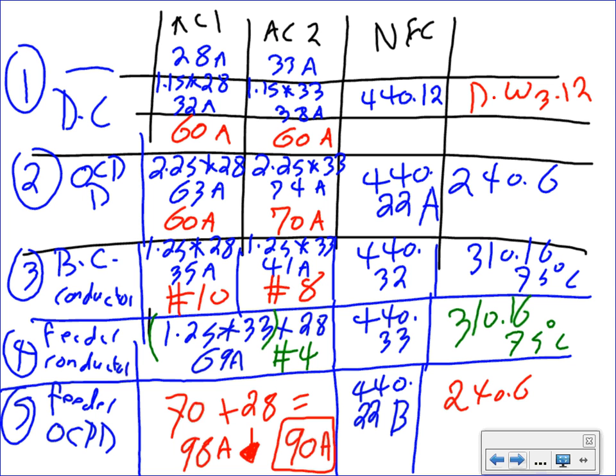What does 440.22A tell us? How to size the overcurrent protection device for the branch circuit, right? So that's what they're referring you to: the branch circuit overcurrent protection device plus the full load current of all the others. Pick whatever you get out of this calculation, which we found, the largest one, which is 70, and add the full load current of everything else to it.